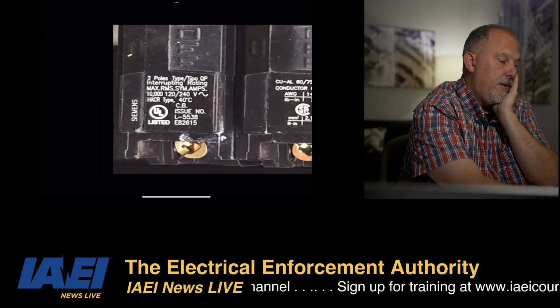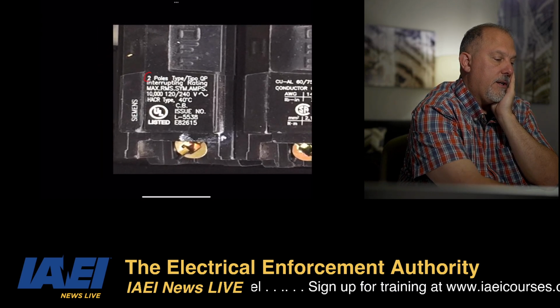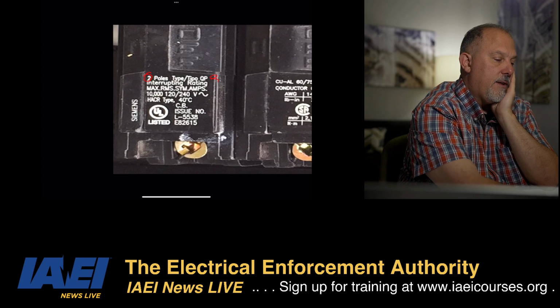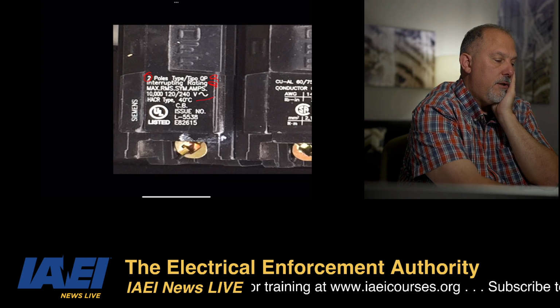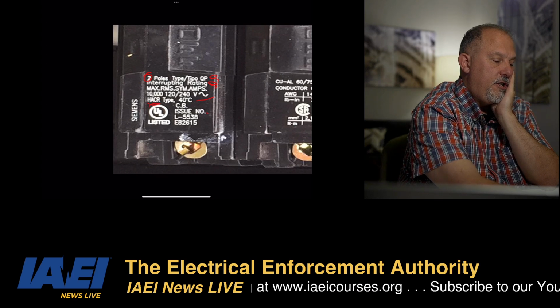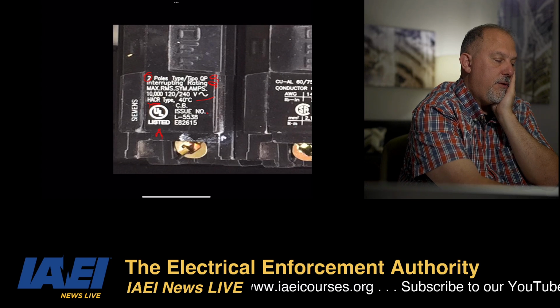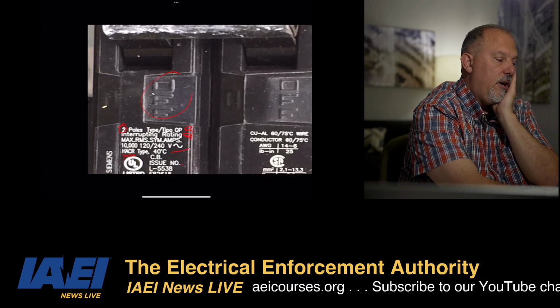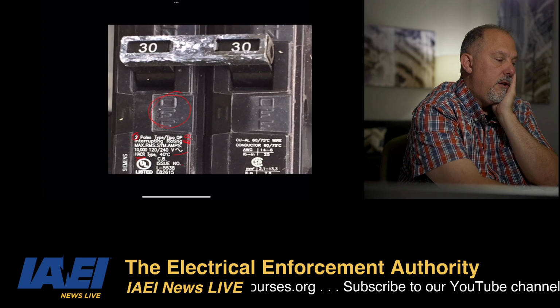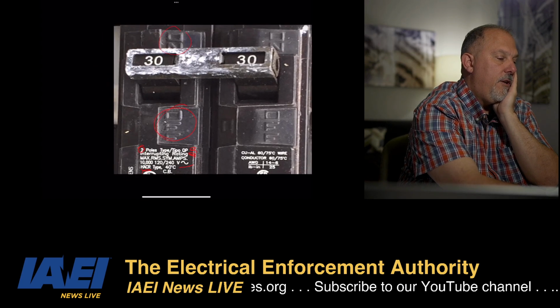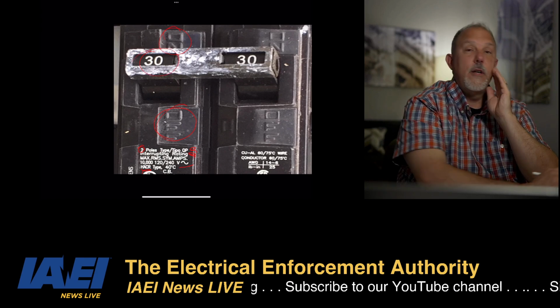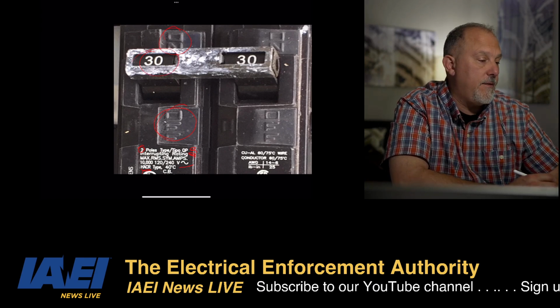Here's another one. This is a Siemens breaker. You've got the number of poles. You've got the type. You have the interrupting rating. You have the voltage, HACR, issue number, etc. The fact that it's UL listed. You have off. And I'm hoping, yep, and you've got on, and you've got the current. A lot of information on the face of this device as well.